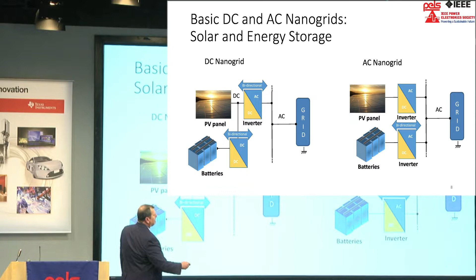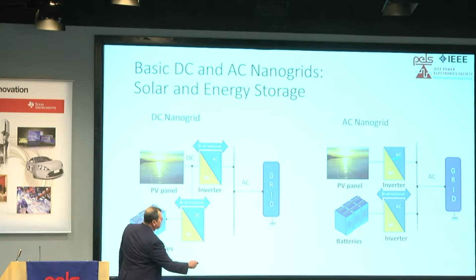And after that, you couple to the AC grid. In the AC grid, you have your PV panel. This inverter is unidirectional because the power always goes from the PV panel to the grid. But then you need another inverter that is bidirectional, and you connect that one directly here. You can have that system earlier, and then come back and put the battery later.